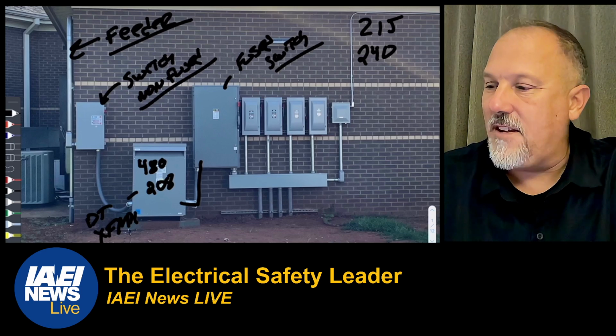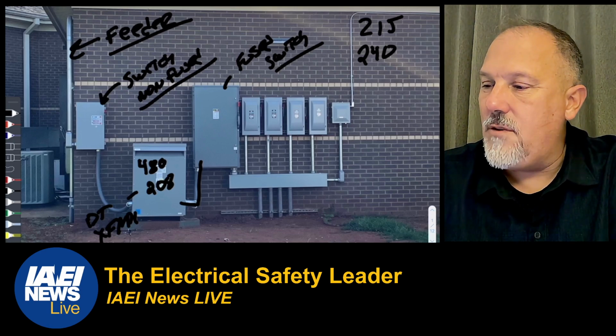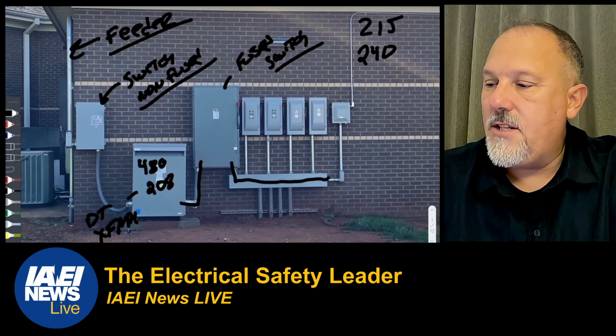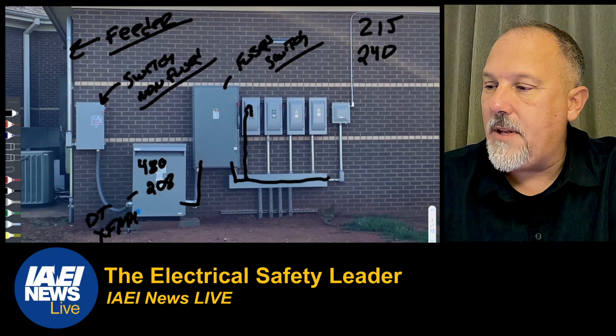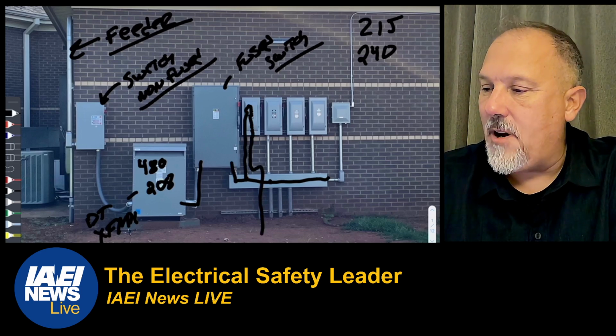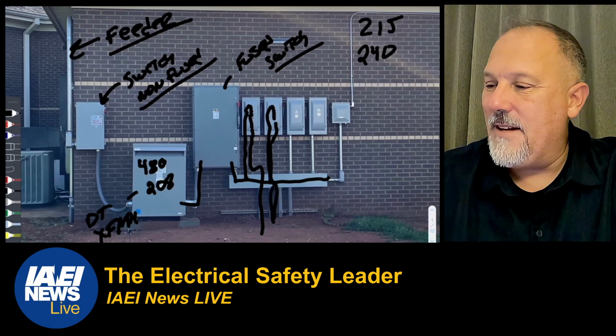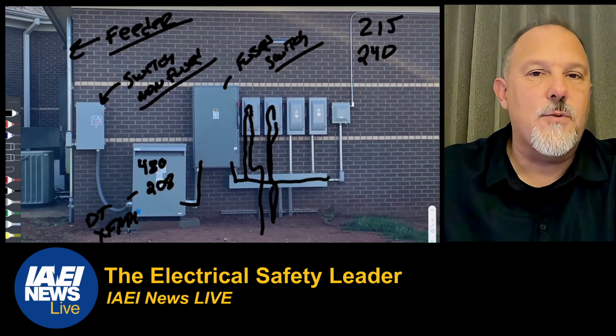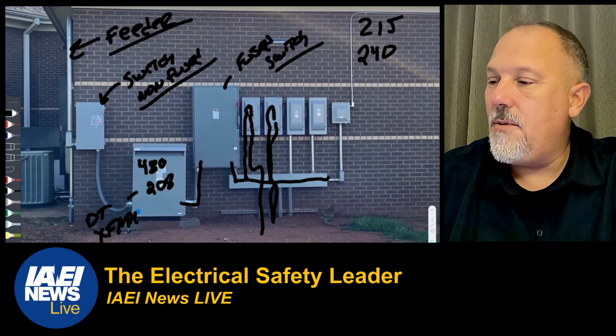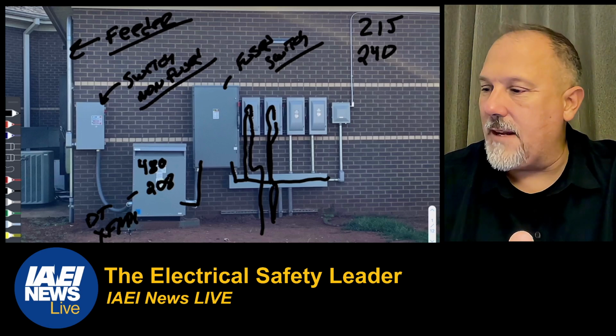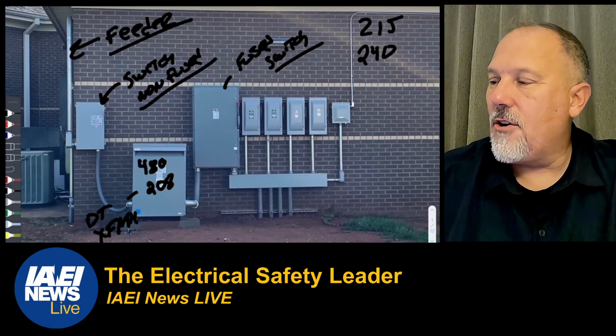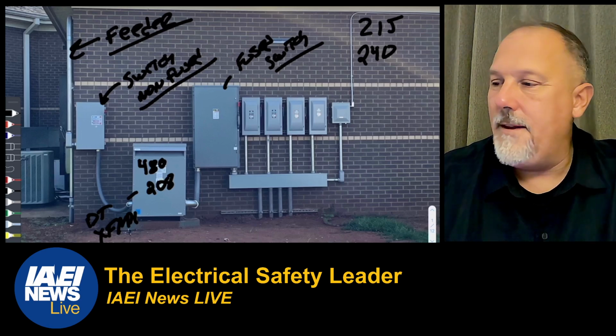but after this fuse switch, what they do is they tap off and they come up into this switch. They come back down and go out. They tap off of this, come up through a fusible switch, come back down through that pipe, and down out to, I believe these are individual dwelling units. So you have the tap rules that you've got to think about. Right, so we got the tap rules. We have Article 215. We have Article 240.